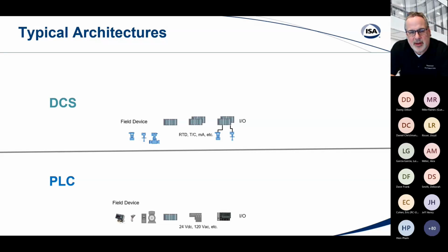We talked a bit about the I/O connections, and Grant mentioned that the traditional PLC is pretty much built based on simplex - non-redundant - whereas the DCS was really built inherently to tolerate failures. So at the controller level on the DCS side, they will typically be redundant, because no single point of failure should shut down a process. We'll talk about that a bit later.